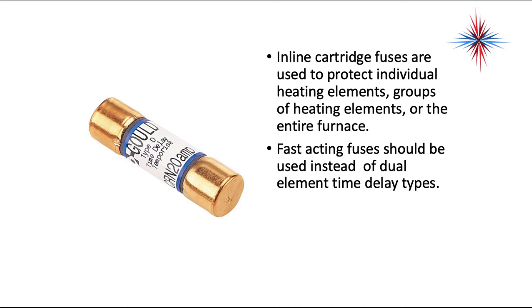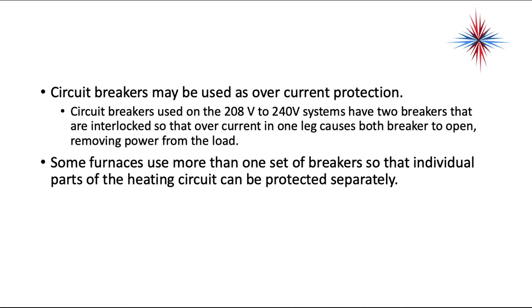Inline cartridge fuses sometimes are used to protect individual heating elements, groups of heating elements, or the entire furnace. These are fast-acting fuses and should be used instead of dual element time delay types. We want fast-acting. Okay, if we have an overcurrent or overheating situation, we have to deal with this fast before there's a chance of fire.